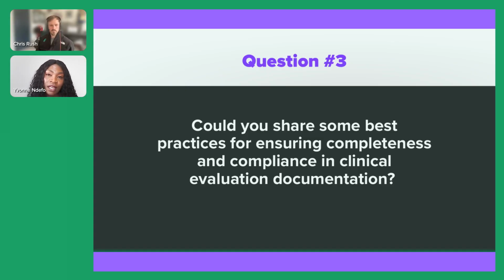Alignment and consistency is another thing. I think I talked about that earlier as well. For example, your intended purpose statement should be the same. There should be traceability across all the documents, and whatever inputs and outputs are going into the documents should be consistent. For example, if you do a literature search and the outputs include complications like infection related to the device or similar devices, you want to assess the risk of infection with your device, and based on that residual risk, link it into your IFU. So I always emphasize alignment and consistency across documents. You want to be saying the same things across these documents.